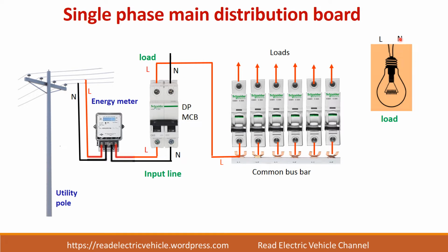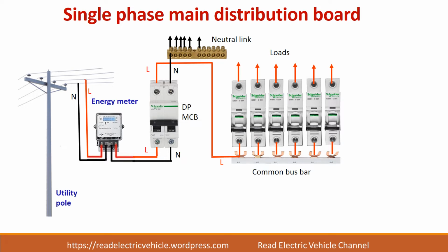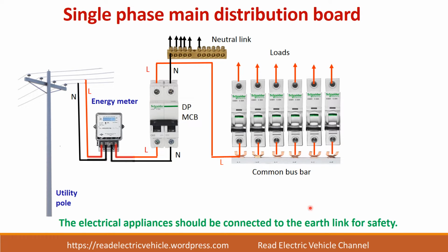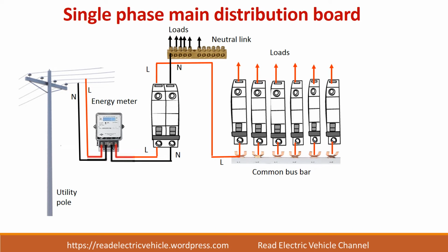Then we have one neutral here in the load, as well as here one neutral is there. So we can connect using a neutral link. All these things will go to the load. For different loads, we will connect all the neutrals of the loads to the neutral link. In addition, we have to connect the appliances to the earth. So you can use an earth link which can be connected to the earth electrode. We have seen how to wire a single phase main distribution board. It is very simple and easy to wire.